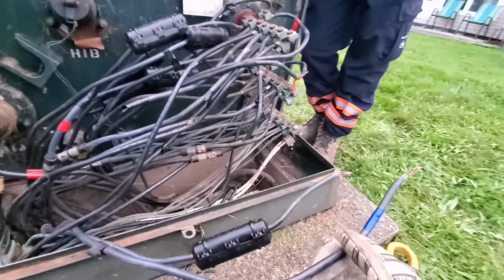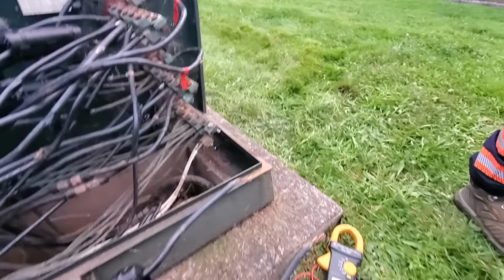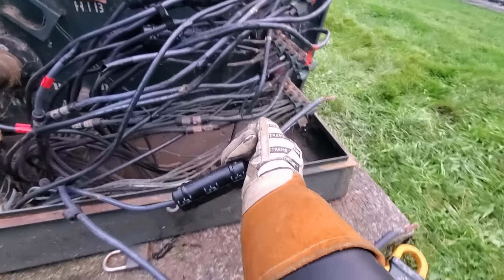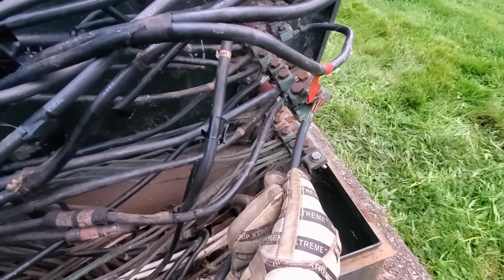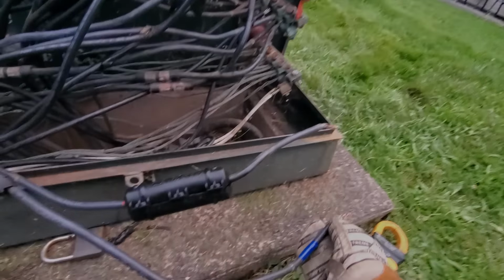Alright, so after multiple leads with 0 amps, these two, we shorted them out in the meter and did a continuity check, and we had continuity between the two. When we hit that guy on the hot, we're getting our 120 at the meter. This guy here on the hot, we're getting 0, and we're picking up on this guy. So that's the bad cable.